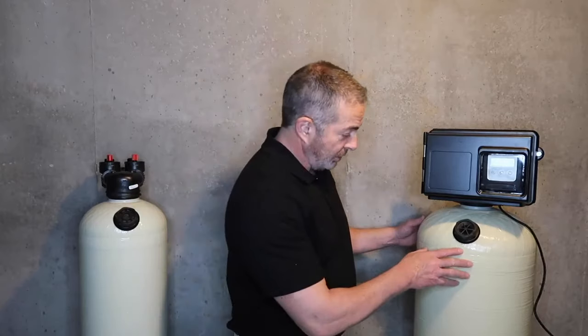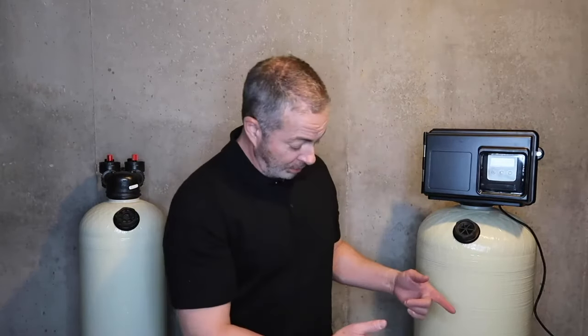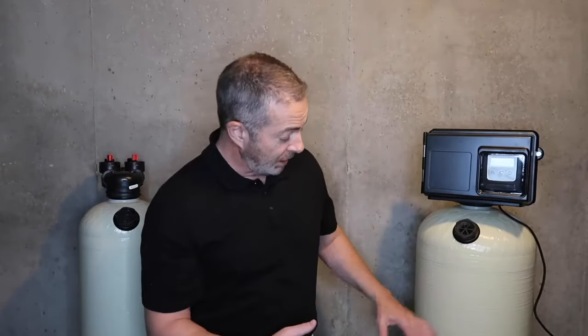So when this backwashes, the water is going to go down the center tube and come up through that Vortech plate, and it's going to move in a circular motion. That will help clean the media bed — whether it's calcite, carbon, or catalytic media for iron filters — doing a much better job of backwashing than the standard gravel-bedded tank with a distributor tube and basket at the bottom.